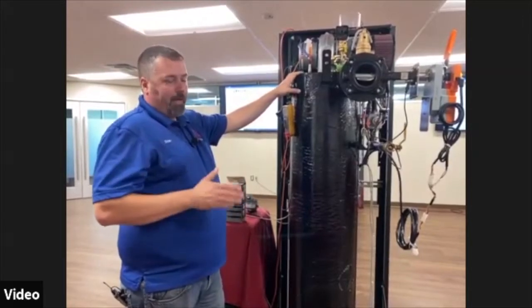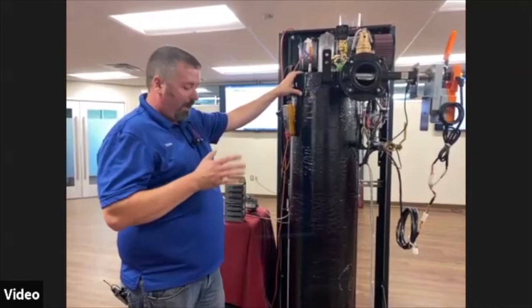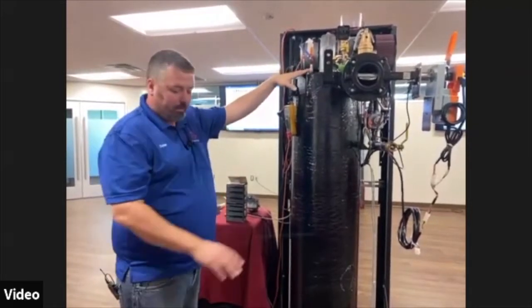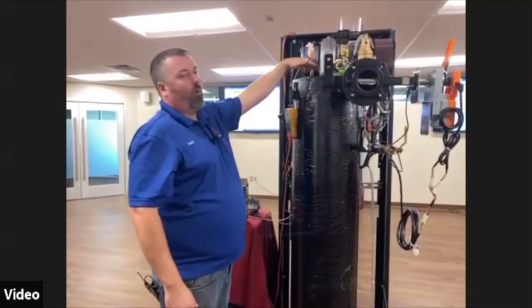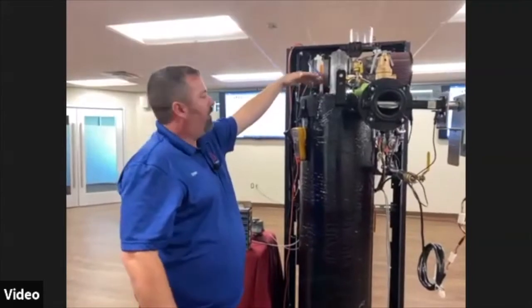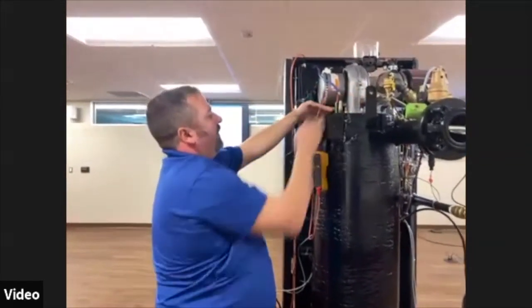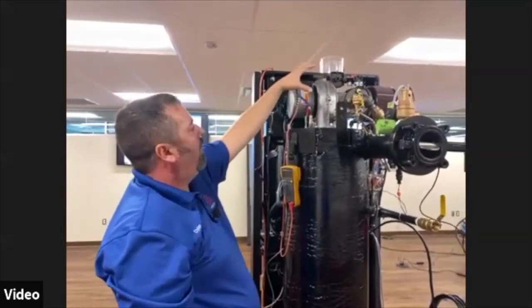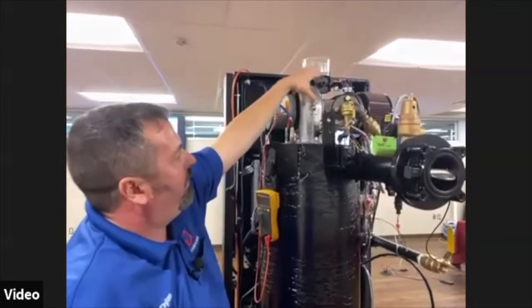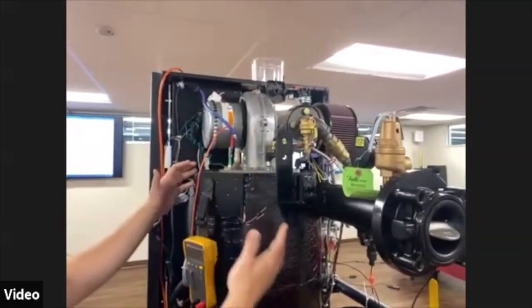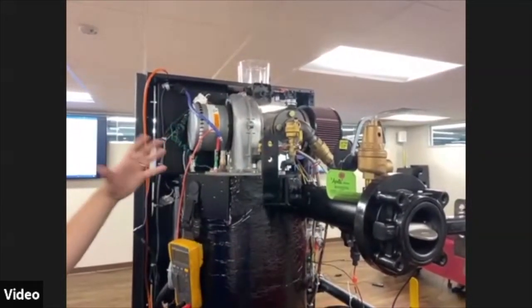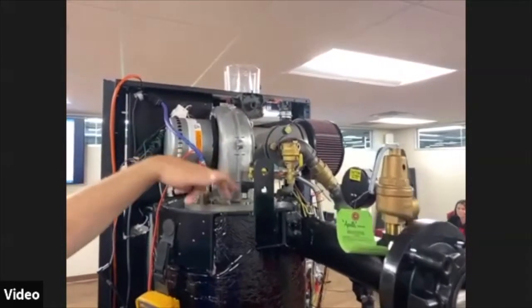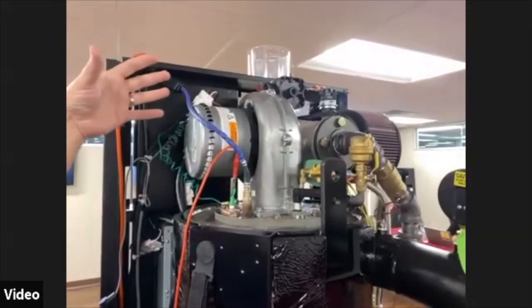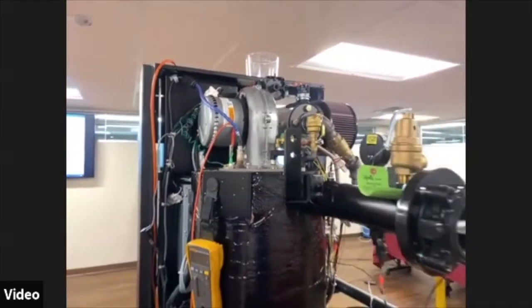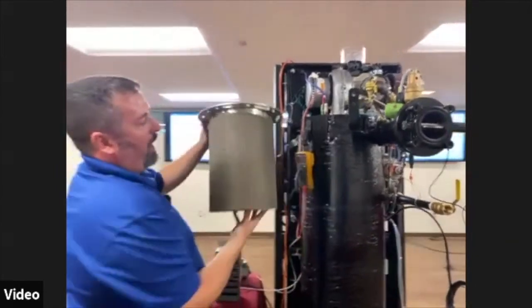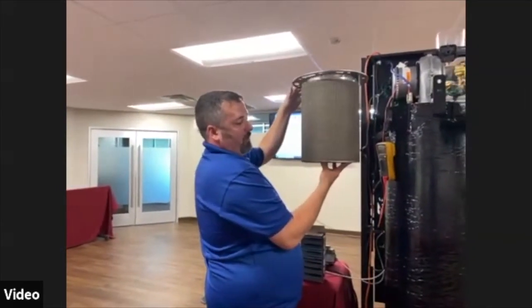Then the biannual maintenance that Aerco recommends, the kits include the same things, the sensor and the igniter and the O-ring, but it also includes gaskets for the burner, because every 2 years they want you to pull the burner, which on this model, you would remove all your ancillary devices, your igniter, sensor, and all that. And you unhook your gas line, and you would remove the whole blower assembly and air fuel valve. On the larger models, there's an air plenum that you remove. It's a little easier because they're larger, but this is a smaller model. And then you remove your bolts around your burner plate, and the burner will pull directly, vertically up out of that hole. I have a burner here out of a larger model. It's obviously not out of this model, just so you can see what it looks like. It is a typical low NOx mesh burner.